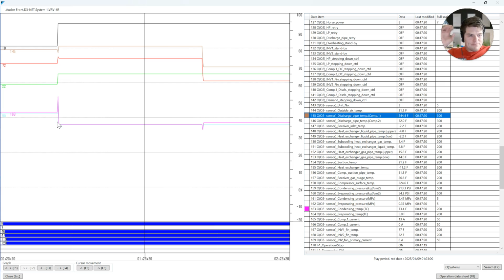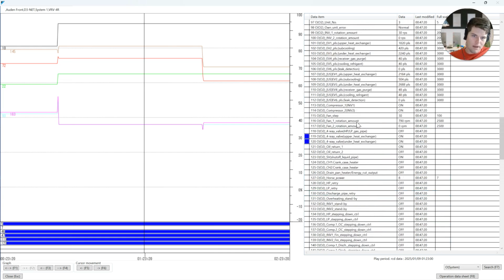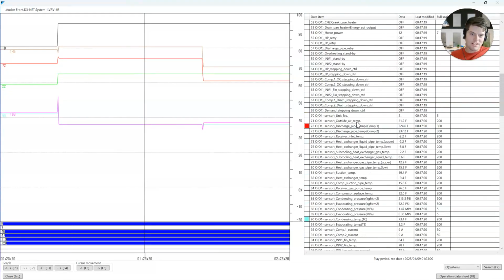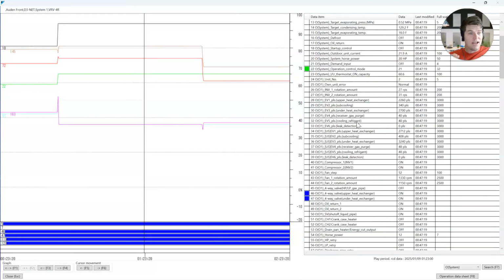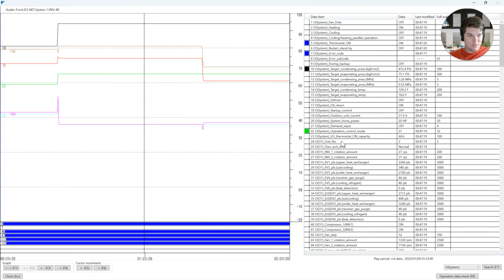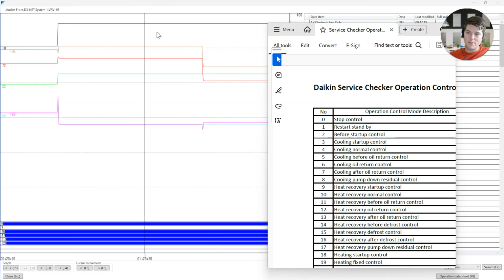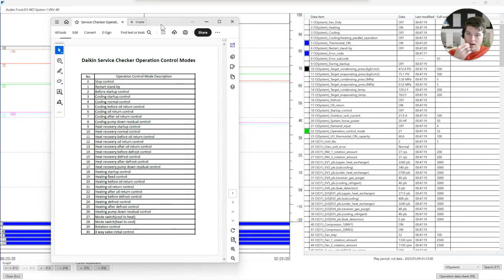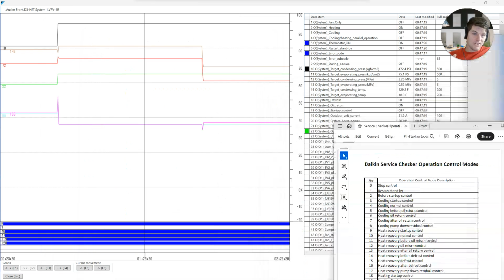Anyways, doesn't matter. So we're going to slow it down and we're going to talk about one of the modes that is designed to protect the system, however, kills compressors in the process if the charge is off, right? And that mode is oil return. Now, everybody talks about it like it's this beautiful process and it's great for compressors. And I would say, yes, it is. We're in mode 21, which is heating oil return control mode, right? Why does it kill compressors?